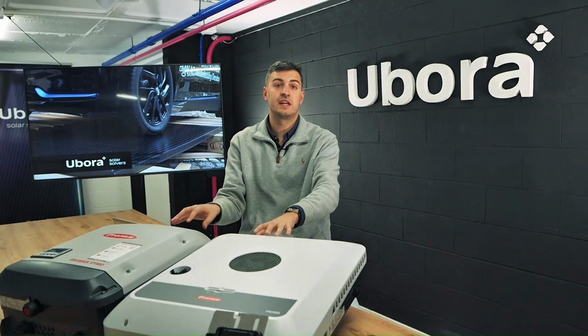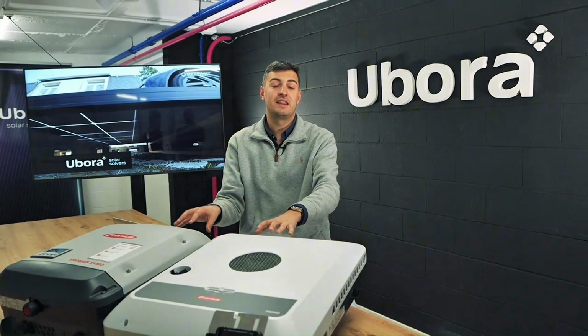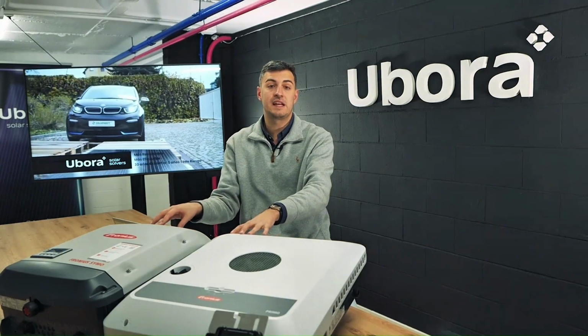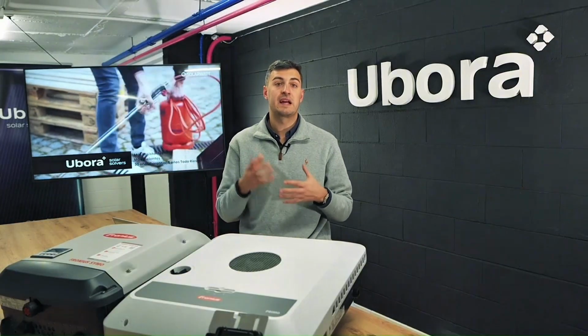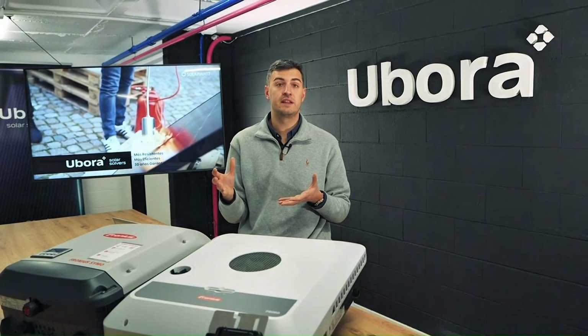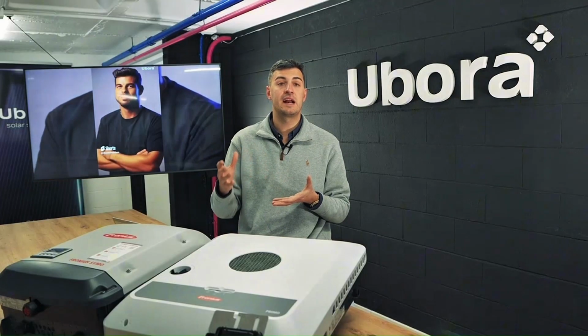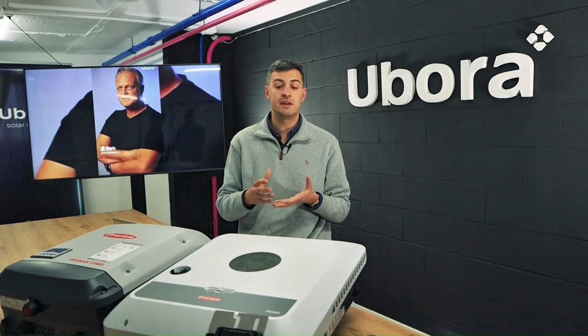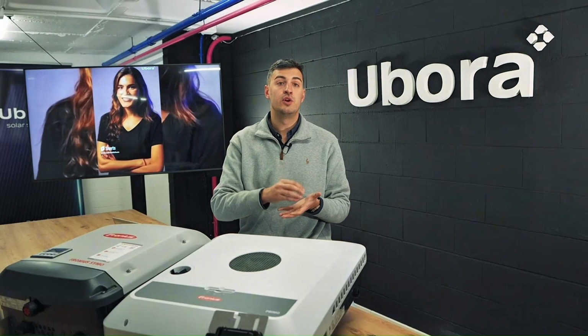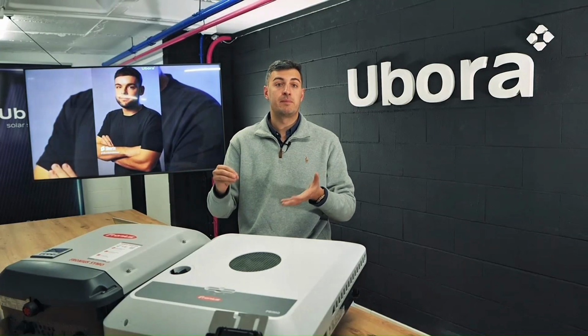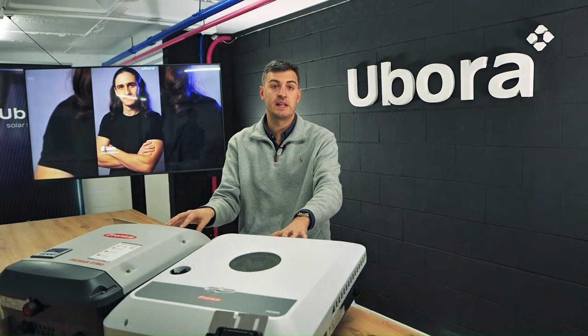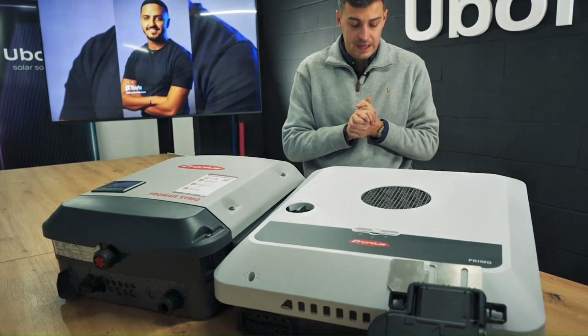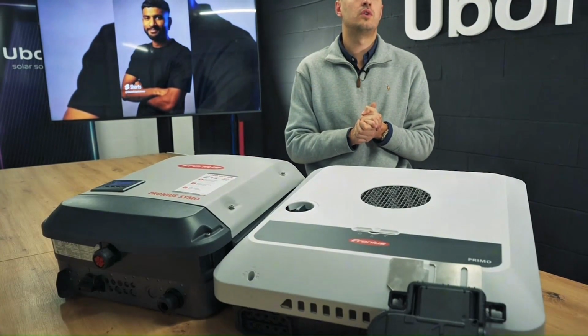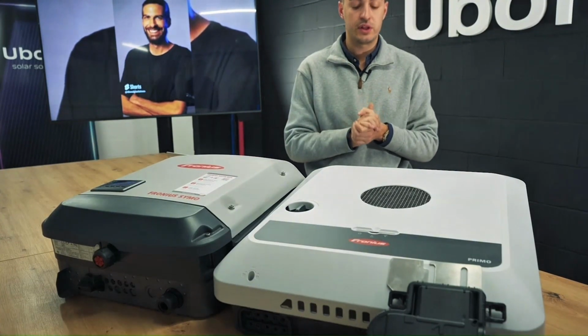Therefore, it is very important that our inverter have at least the different MPPT inputs required, depending on the orientations, so that each orientation has a different input. And thus the voltage that each orientation generates, with the MPPT management always guiding us, yields the maximum power point to enable converting that energy, and so that the efficiency or the energy production capacity of our system increases.